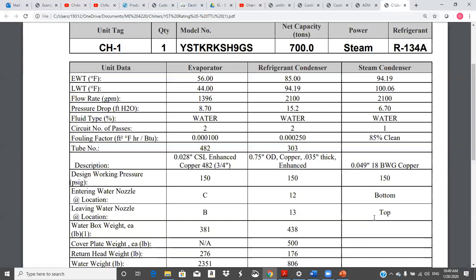Rated flow, evaporator, 1396. Okay, so something to think about is GPM per ton. I don't even need my calculator for this. So we got 700 tons. What's the GPM per ton, roughly? 2 GPM per ton on the evaporator side. Okay. Let's see, flow rate, condenser. I can do that math. Divide 2100 by 700. That's 3 GPM per ton. Okay.